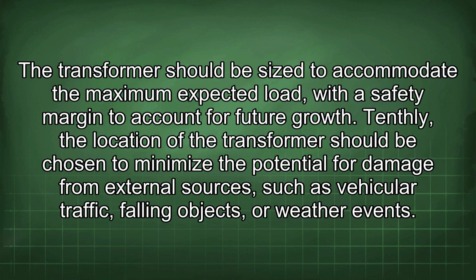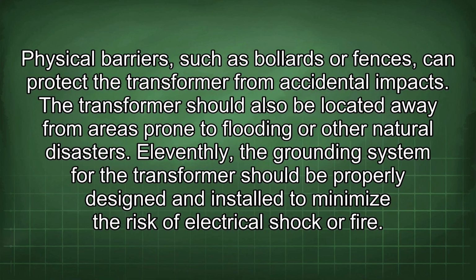Tenthly, the location of the transformer should be chosen to minimize the potential for damage from external sources, such as vehicular traffic, falling objects, or weather events. Physical barriers, such as bollards or fences, can protect the transformer from accidental impacts. The transformer should also be located away from areas prone to flooding or other natural disasters.